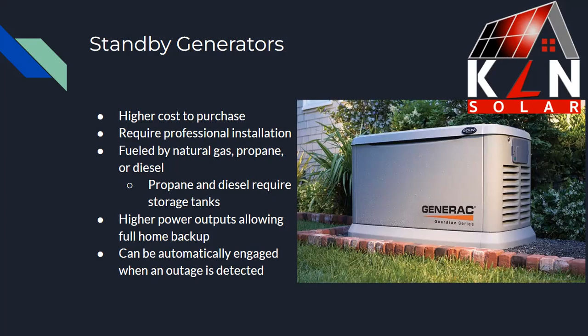They do have a higher power output. Most typically we'll see 20 kW or 22 kW generators, which can get you a fairly easy whole home backup sometimes. And they can be automatically engaged, at least the better, higher-end ones. So you have an outage, there might be a couple second delay, and they fire up and kick in and out automatically through an automatic transfer switch.